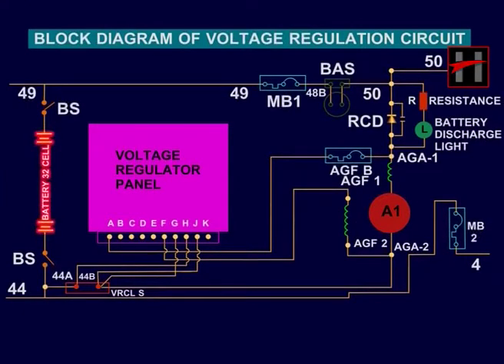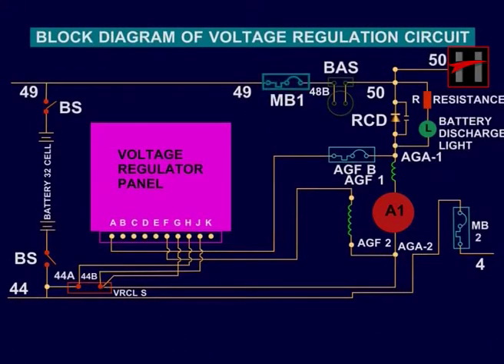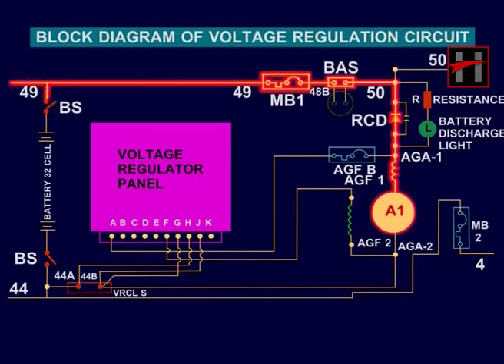Battery is provided as backup supply for control and auxiliary load. The battery is connected between cable number 49 and cable number 44 through battery switch BS. The battery ammeter shunt, or BAS, is connected between cable number 49 and cable number 50 through circuit breaker MB1. The battery is charged by the auxiliary generator when the diesel engine is running.